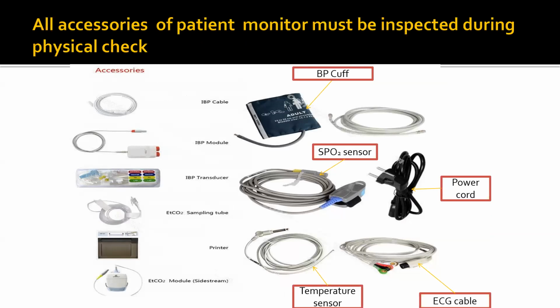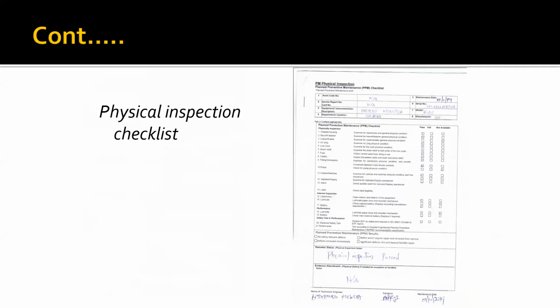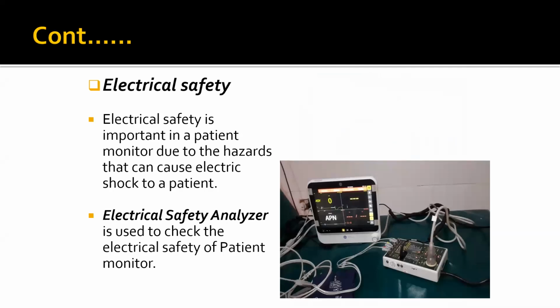So these are all the accessories that you're going to see on the patient monitor, like the SpO2 sensor, power cord, temperature sensor, ECG cable, BP cuff. BP cuff, you need to clean. Sometimes people overuse it until the cuff cannot strap properly, so you need to clean all that. Sometimes you need to replace the cuff. Physical inspection is basically a checklist used to check all the physical condition. This is a standard checklist that is used in Tanzania as well. Yeah, we're also using it.